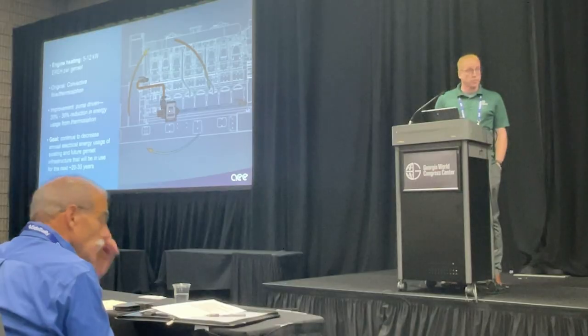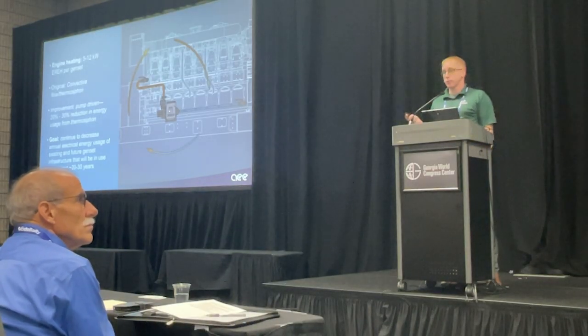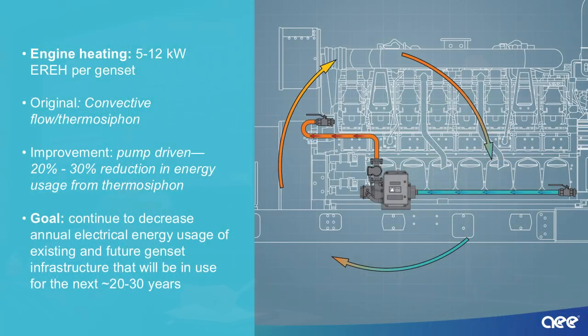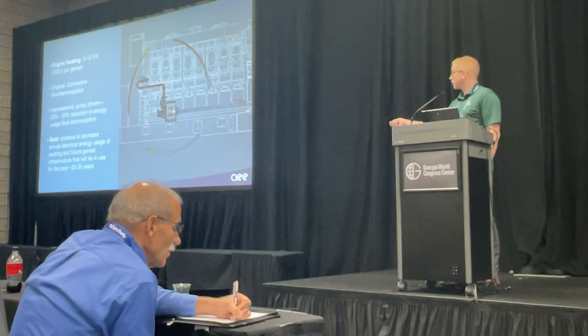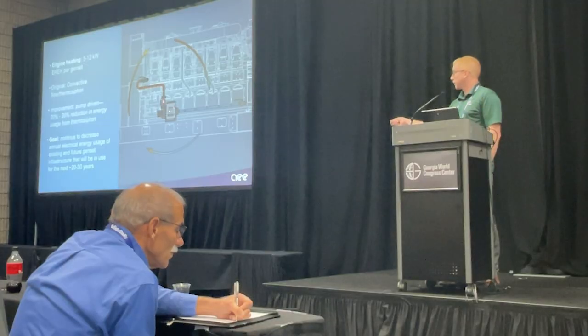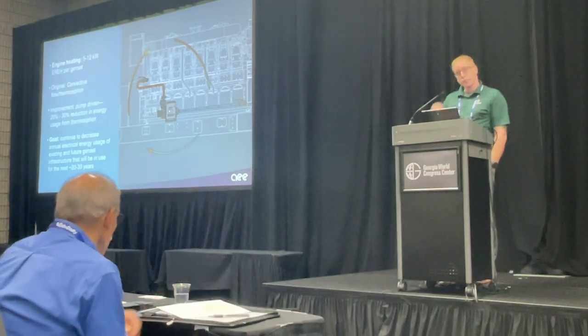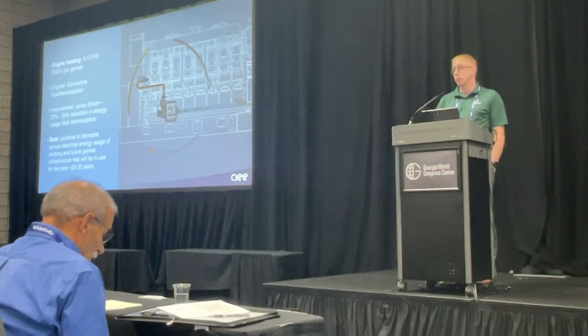We've established that genset engines need to be heated, typically with a 5 kilowatt or 12 kilowatt electric resistance engine heater. The most basic system is a tank outside the engine with a hose from the bottom of the engine to the tank inlet, an electric resistance element inside, and an outlet. As the element heats the coolant, it rises to the top of the tank, heated to near boiling, while cold coolant from the bottom returns to the heater.